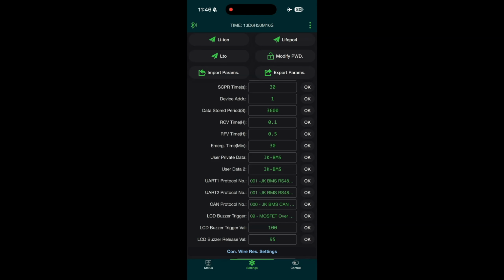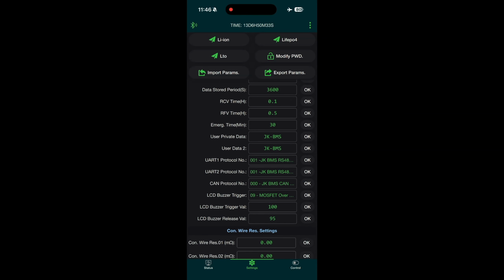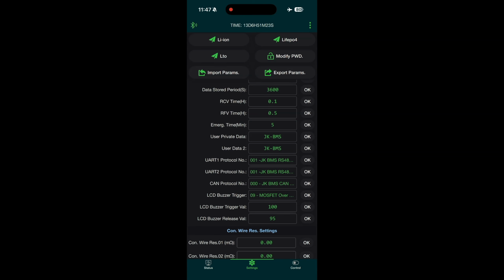Okay, next one down is the emerge time minutes. Again, it's in minutes. This is a timer that if you turn on the emergency mode in the control, it will wait 30 minutes until it will turn it off. Now, the emergency setting is basically where, if you turn it on, it's going to ignore most of these safety settings, so your over voltage, your over current, all that sort of stuff. If you don't need to turn it on, I recommend that you don't. But this is a timer that if you turn that on, it will wait for this long and then turn it off. I think that 30 minutes is a long time, so I'm just going to change this to 5 minutes. So basically it'll ignore these safety parameters for about 5 minutes, and then it'll reactivate it.